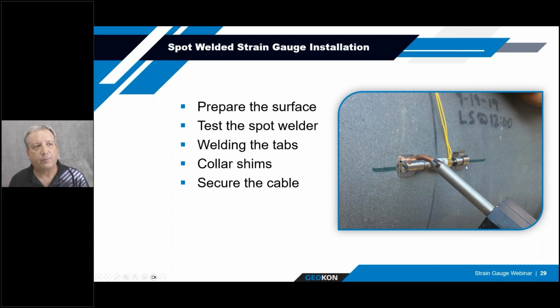They've put a collar strip, hanging off this other end, over both ends to help secure it and provide additional connection to the subsurface. After the collar strips are welded in, you put a little cover over the gauge, like a half round, and then collar strips again over that to hold it in place. Then you tuck the wire into the cover and put a strip over the signal cable to hold it in place so it doesn't pull out from the instrument if anyone puts force on it.